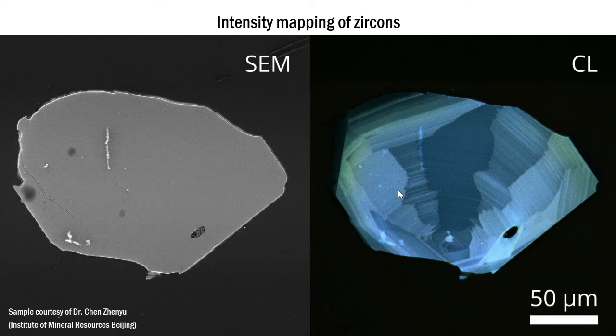Another detector setting that's important is the image resolution. This image has 2048 by 2048 pixels. Now, you could acquire an image with more pixels, say 4096 by 4096, but you would again need to compromise on the speed of the acquisition. So once again, given the feature sizes and the dimensions of the zones, we can see that 2048 pixels is good enough. Also important to point out here is that this is an RGB image, not a panchromatic one. It was acquired with three color filters, which means that you always have lower signal each time than with panchromatic imaging. So if you perform panchromatic imaging with this sample instead, you could use an even lower dwell time than 40 microseconds and acquire faster.